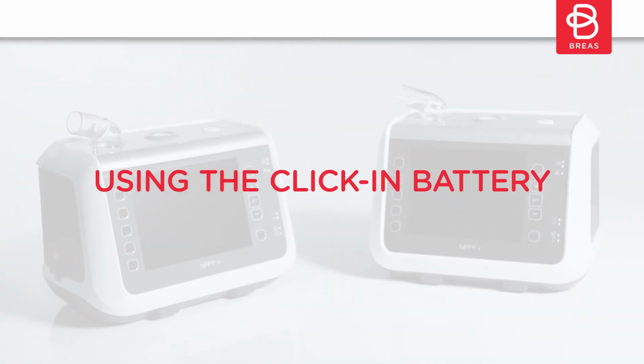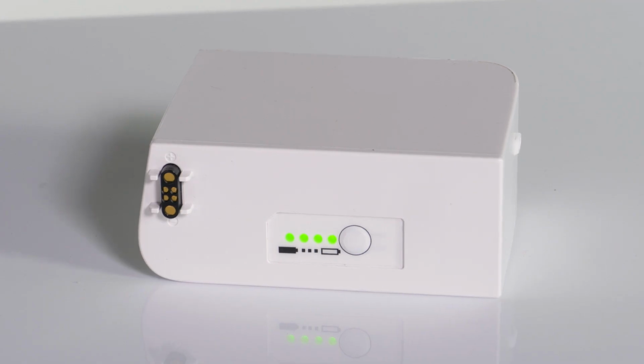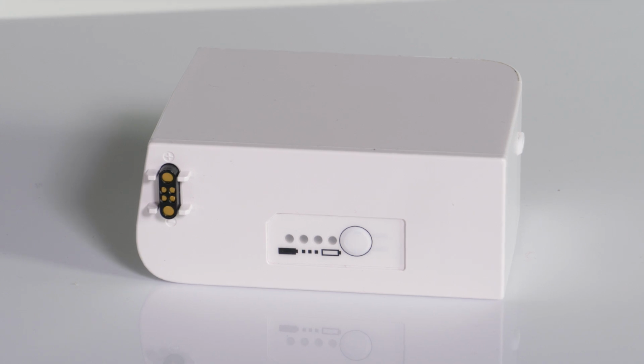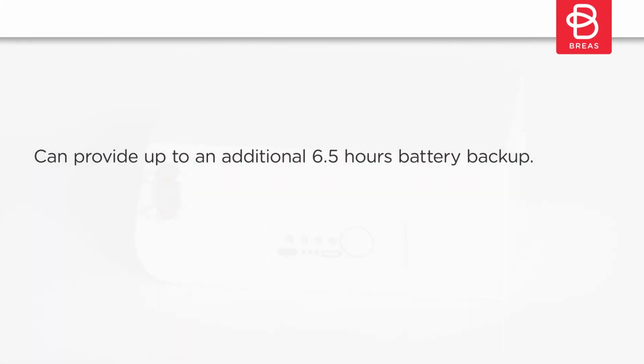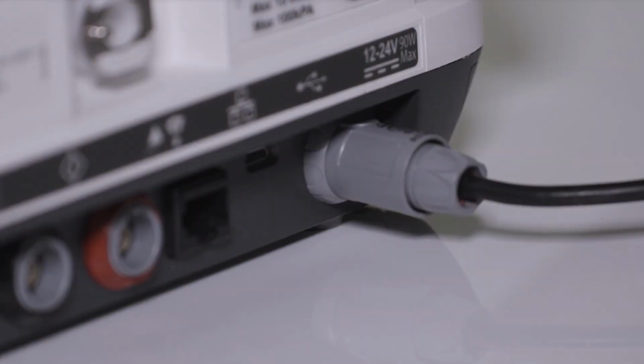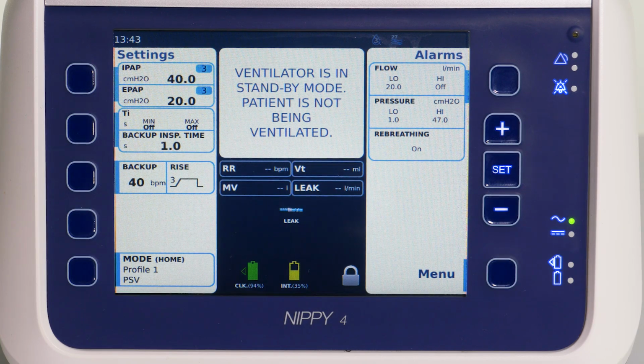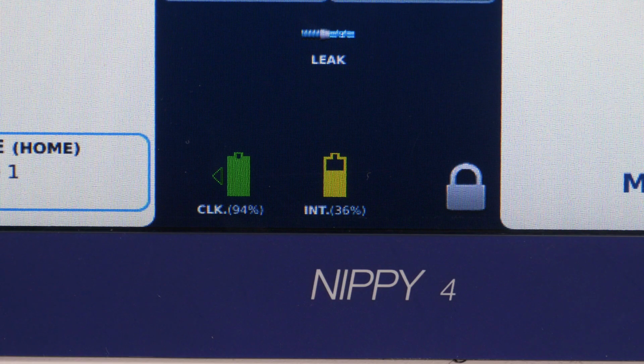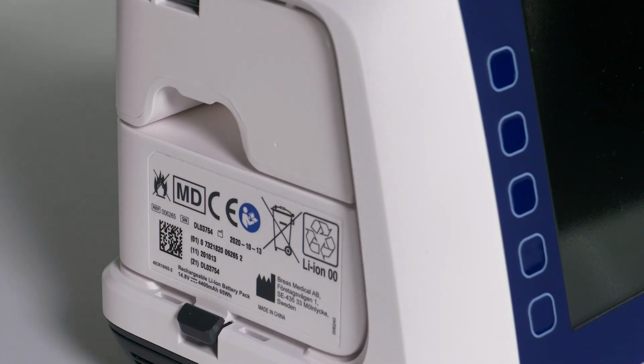Using the click-in battery. Additional click-in battery packs can be added to the device and can provide up to an additional 6.5 hours battery backup. These batteries will charge when the device is running on mains power. The status of the battery can be viewed on the screen with a percentage given for how much battery life is left for both the click-in and internal batteries when connected to live power, and hours, minutes available when operating on battery. The ventilator will use the click-in battery as its first option before switching to internal.